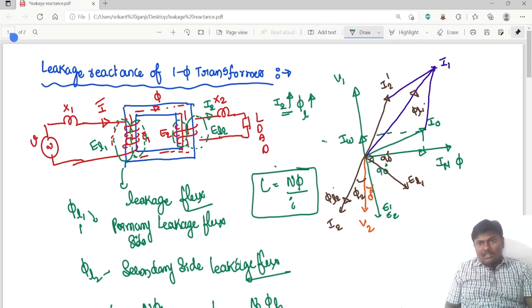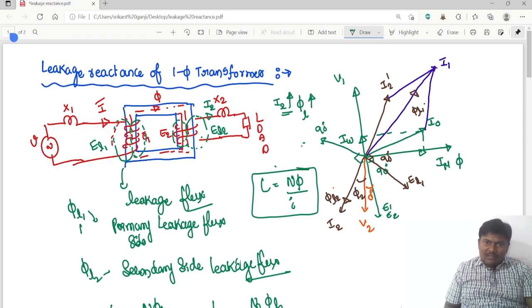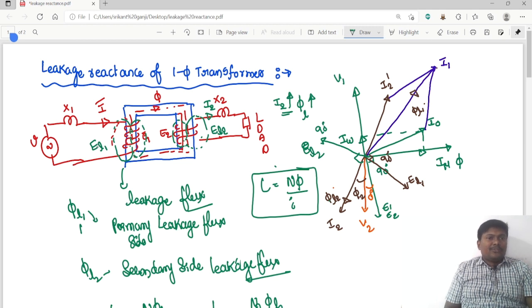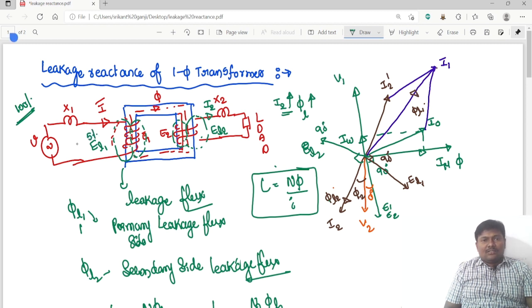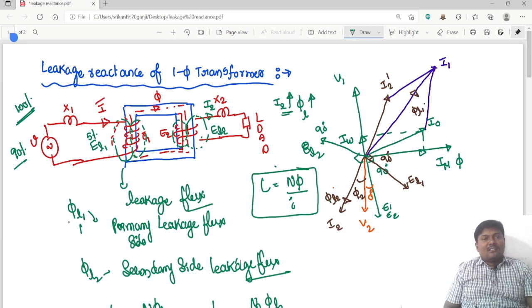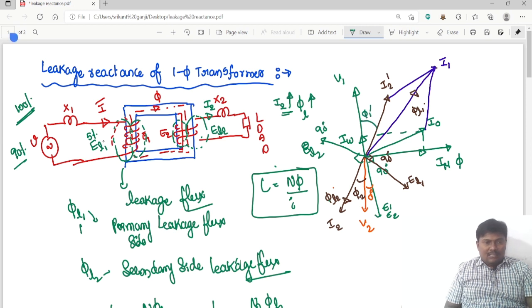Due to I1 the leakage flux phi_L1 is produced, and due to I2 the leakage flux phi_L2 is produced. If I2 increases, I1 also increases. With respect to phi_L1, an EMF El1 is induced exactly 90 degrees to I1. Similarly, El2 is 90 degrees to phi_L2. For example, if 100% of flux is present and 5% leaks, only 90% is common to both windings — that is the useful flux. The flux which links either winding but not both is called the leakage flux, represented as phi_L1 and phi_L2.